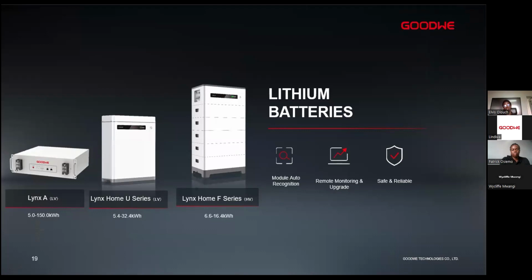Then we have our Lynx F series. One module is 3.3, but you normally put at least 2 modules. That's why we have the 6.6. And one tower can carry 5, which gives you 16.4. But you can parallel them to give you up to 132 kilowatt hours. For batteries, they do have module auto recognition, remote monitoring and upgrade, as everything is done through the inverter. And it is safe and reliable because they use lithium technology.